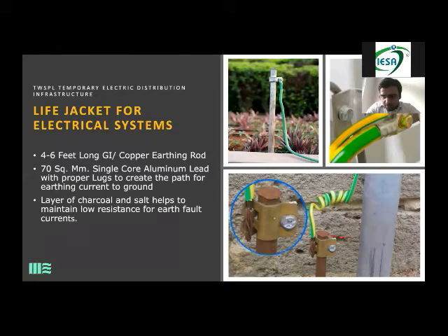What happens is that if you're using undersized wiring, you will definitely get a power loss, or rather a voltage loss. If you're using the right size of wire for the size of the genset, there is no loss. It always depends on two or three factors. One factor is how much load you are putting on the cable. Normally for events, we are not overloading the cable. In the case of an undersized cable, it could be overloaded.